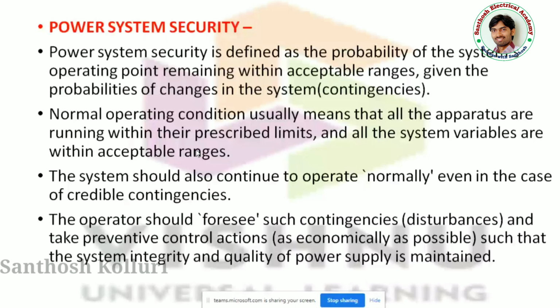So the point is given here. The system should also continue to operate. This is the point that I have explained so far. The system should also continue to operate normally, even in the case of credible contingencies. These are called credible contingencies. And in the switchgear protection subject, you are going to discuss all these things. The operator should foresee such contingencies and take preventive control actions as economically as possible, such that the system integrity and quality of power supply is maintained.